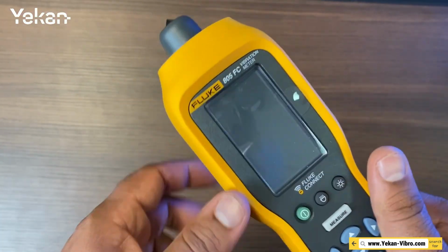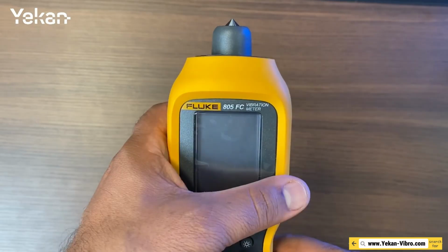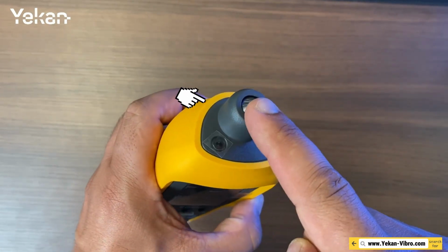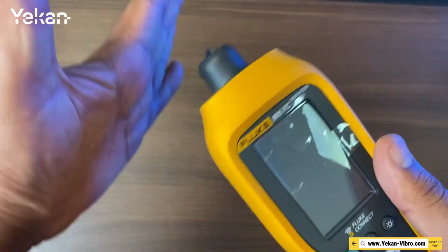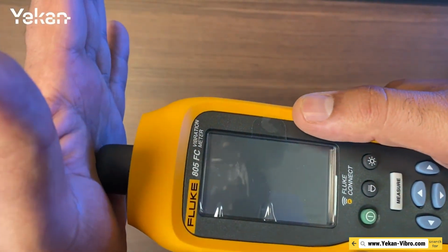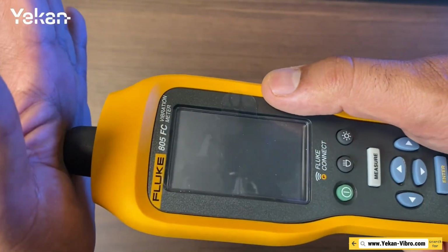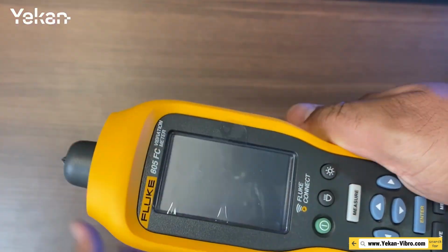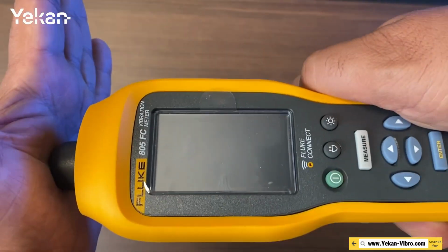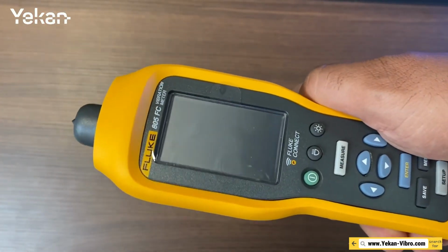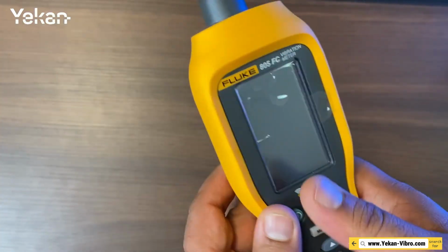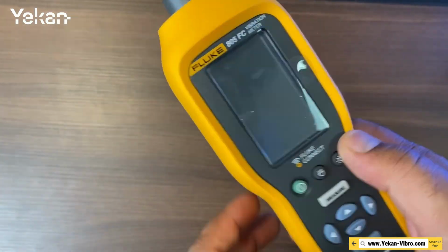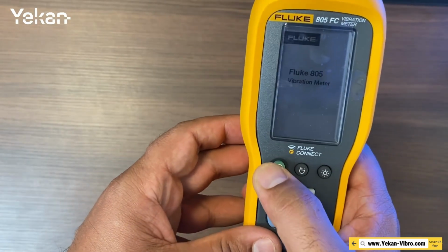In the Fluke 805, both FC and non-FC versions, there is a pressure sensor built in underneath, which we will check together. If I hold it with a certain pressure and another person holds it with less pressure, the device detects this and will not take the measurement. It tells you to apply more pressure. Other devices do not do this, and you end up seeing two different values. Let us turn it on.